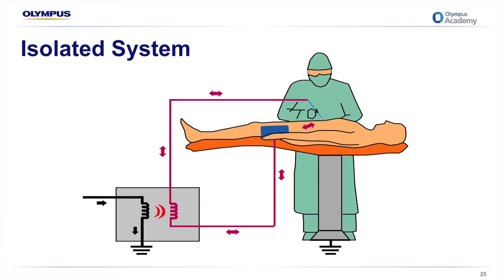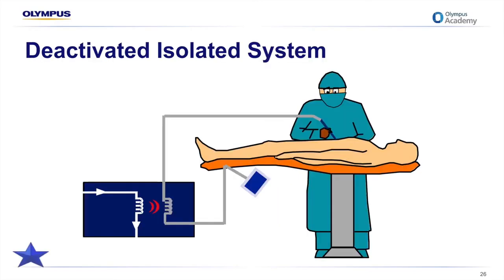Like a grounded generator, an isolated generator without a contact quality monitoring system uses return electrodes that may consist of a metal plate that is coated with a conductive gel, a return electrode with a dry conductive adhesive surface, or a return electrode coated with the preferred hydrogel adhesive that is high in moisture content. All of these return electrodes have a single plate configuration. The generator won't function if the patient return electrode is not placed on the patient because the current is unable to complete the circuit back to the generator.